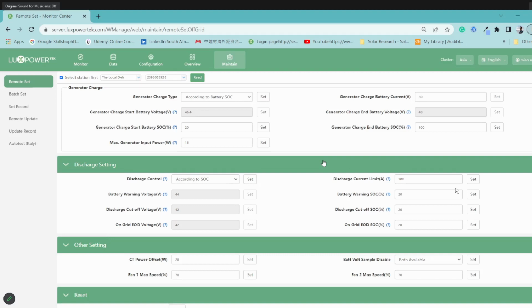What battery is it? It's on a Pylontech system. Okay, I'd like to gain access to the BMS to have a look at the voltage readings from all 16 cells, to see if perhaps one of the cells has a balancing problem, not balancing properly, which could also cause something like that. So there might be a bit of a problem with the battery, but we also need to look at the settings. Is this still a problem you're facing now?